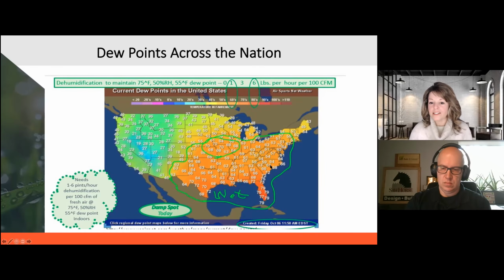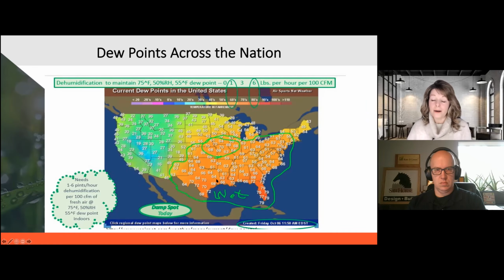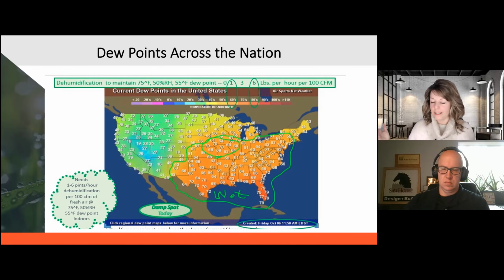But what we can see here is, everybody always talks about, oh, if you live down south, you must need a dehumidifier. Well, the reality is, let's say it's August down south and you've got temperatures in the mid 90s, and you've got standard construction. I'm not talking about a tight home. You're probably running enough AC during that time to get some pretty good water removal.